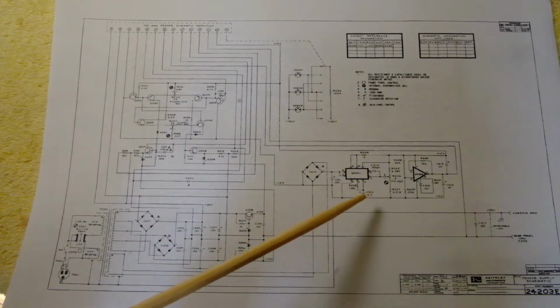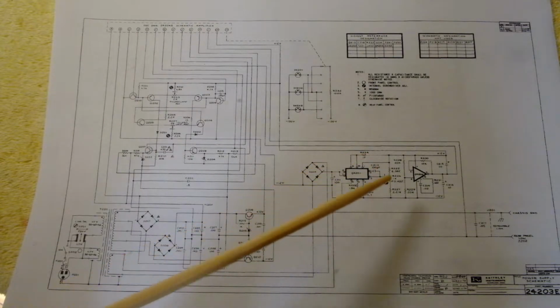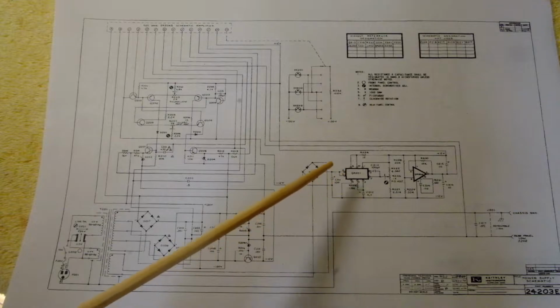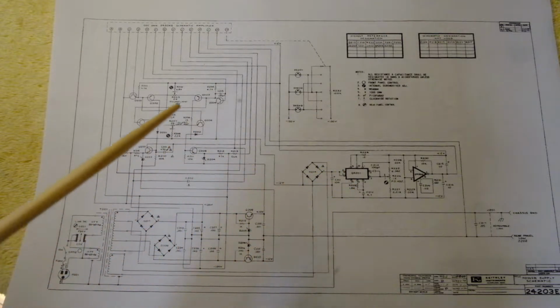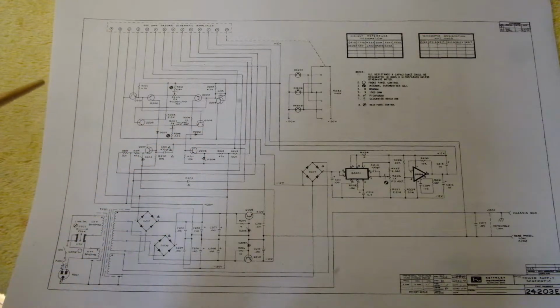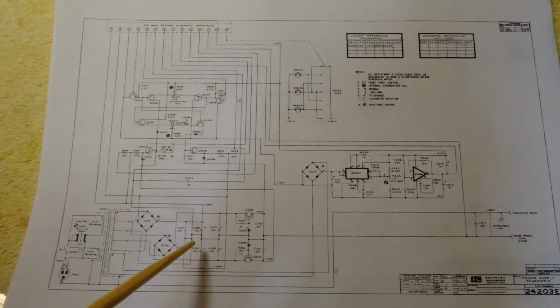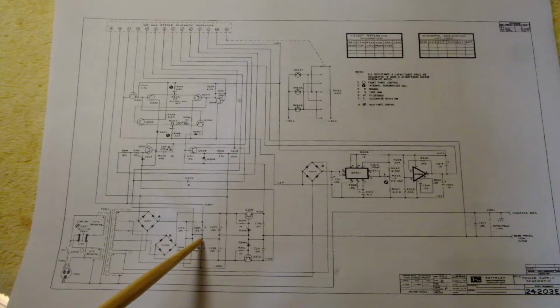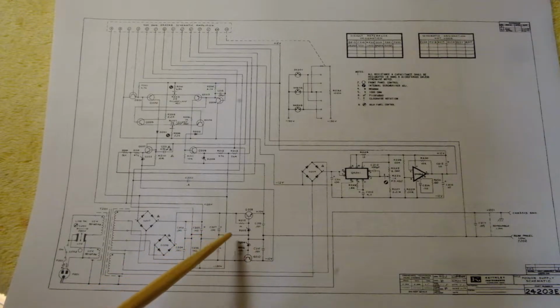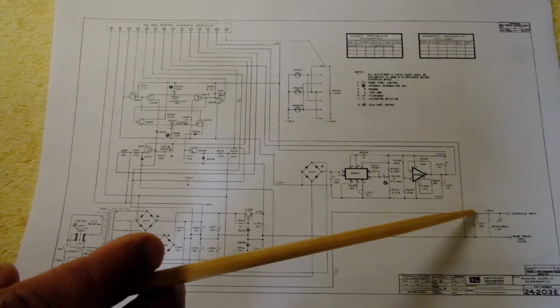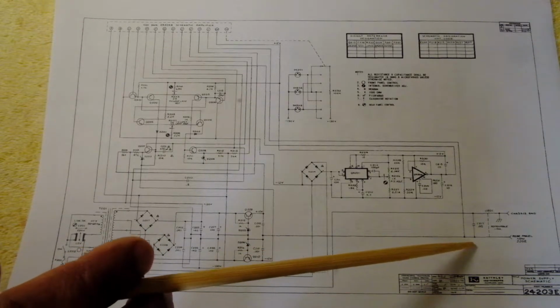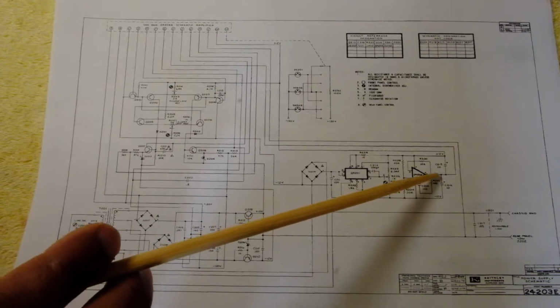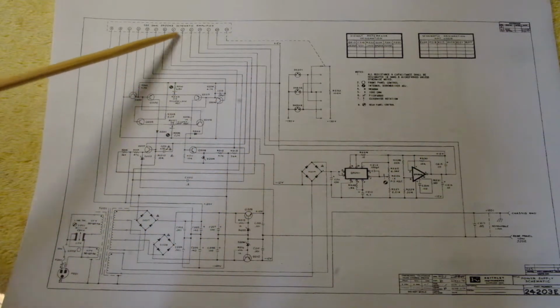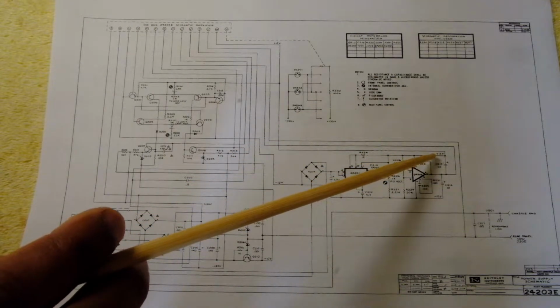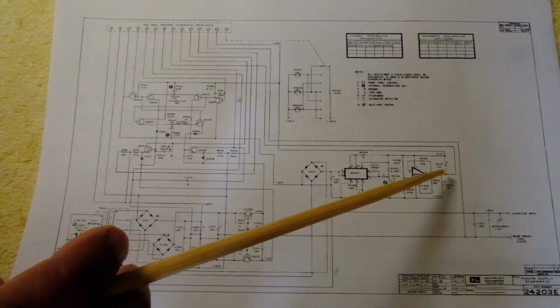This is the most critical supply in this particular instrument, and this determines the functionality of this instrument. If you look at the overall picture of how it works, these outputs are basically referenced to ground, that is, the center tap of these bridge rectifier outputs are all grounded if you connect the chassis to the low output of this instrument. But this particular output here is called the common, which goes to the main circuit board, and the common is used to basically drive the output current into the load.